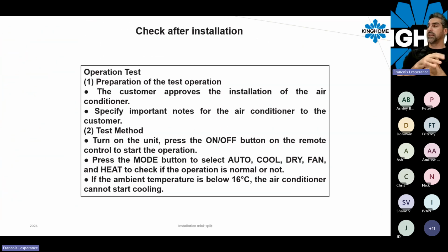When you do some tests, make sure you test every mode: heating, cooling, dehumidifier, and the fan, testing all the fan speeds to make sure they are working properly. And just a small reminder: it depends on the indoor ambient temperature. The remote stops at 16 degrees Celsius, so if the room is below that, you will not be able to start the cooling. But whenever the room temperature is over 16, you will be able to test pretty much all the modes and all the settings.